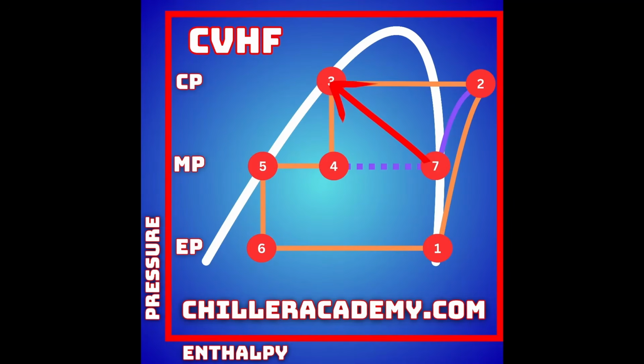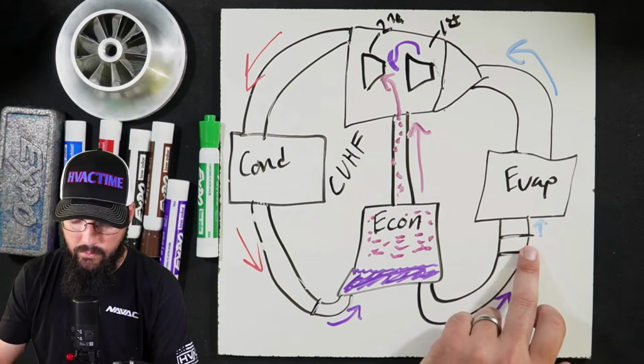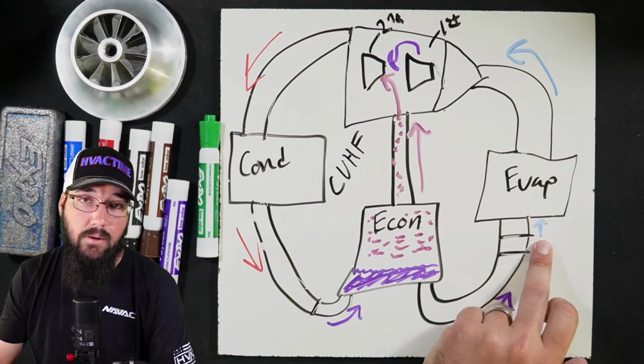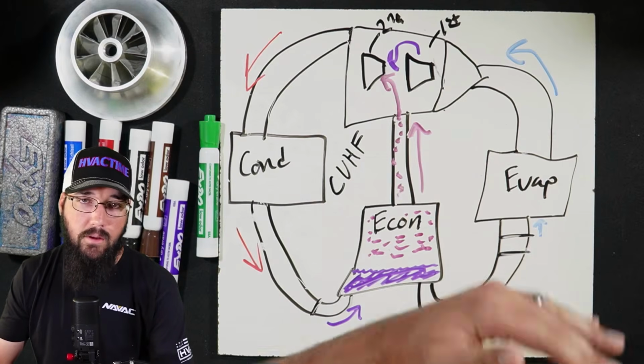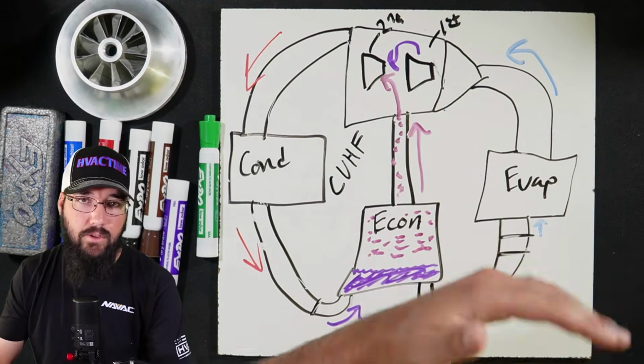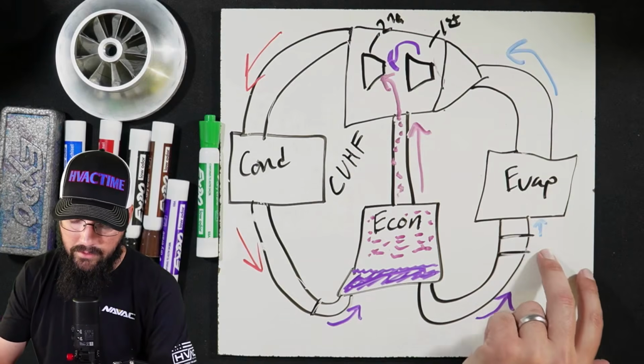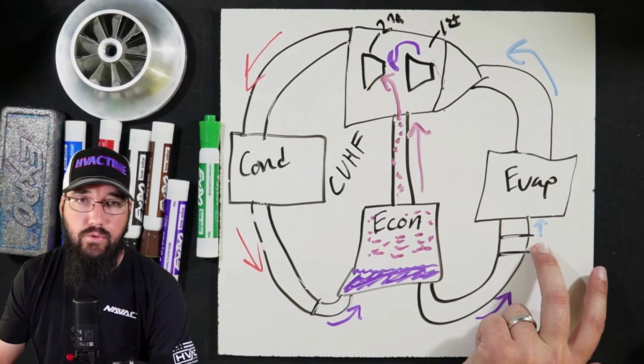Because if we would have gone straight from high pressure liquid to low pressure on the evaporator, you'll see how much further over to the right we are in our heat curve. So by doing this, we dramatically improve how much heat the liquid refrigerant can take in. So from 5 to 6, this is the next flash plate we go into, which is right over here. So these machines actually have a dual plate coming into the evaporator. It's about how the machine manages different load states, low load versus high load, and maintaining efficiency. Point is, there's 2 here.